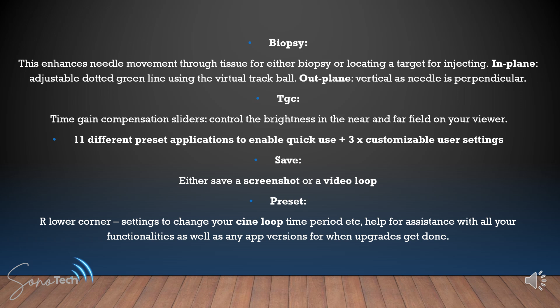So what did I mean about the video loop or the cine loop? You have an option of recording any of the visuals that you're looking at, and this runs in the background. You have an option of recording from 100 frames, which is equivalent to about 10 seconds, to 1,000 frames, which is almost 100 seconds. This is continuous motion, which captures everything that you've just been looking at. This provides comprehensive documentation, which enhances your diagnostic accuracy.